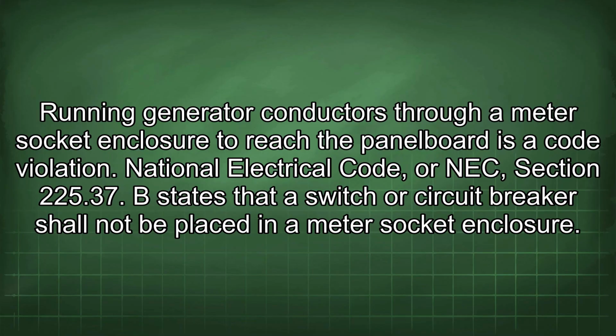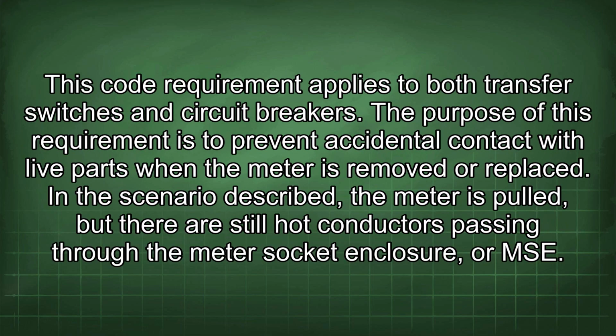Running generator conductors through a meter socket enclosure to reach a panel board is a code violation. National Electrical Code, or NEC, Section 225.37(B) states that a switch or circuit breaker shall not be placed in a meter socket enclosure. This code requirement applies to both transfer switches and circuit breakers. The purpose of this requirement is to prevent accidental contact with live parts when the meter is removed or replaced.